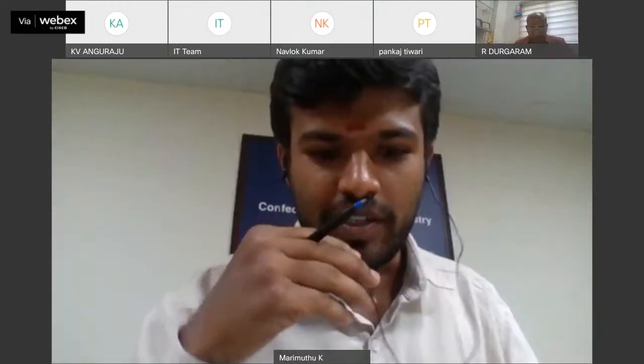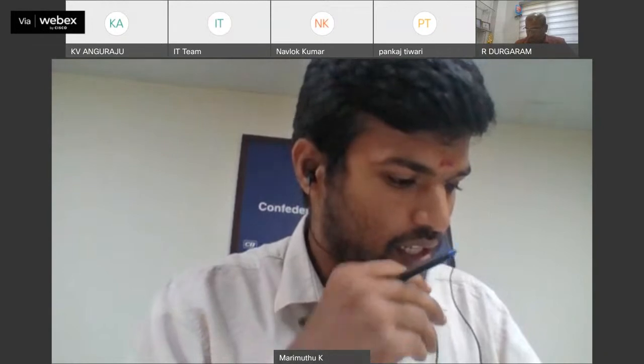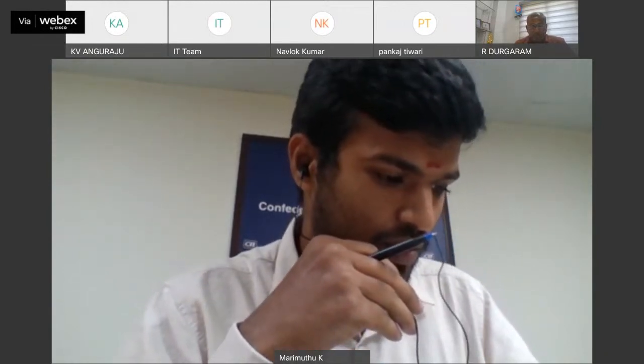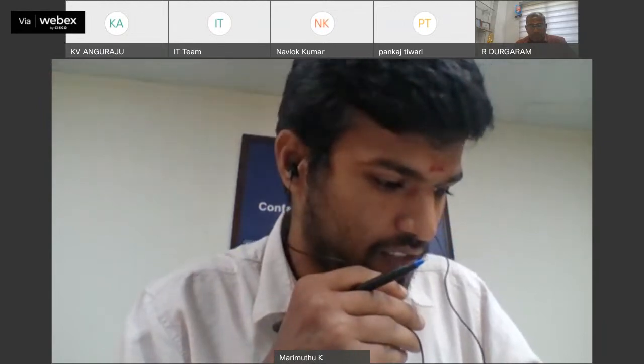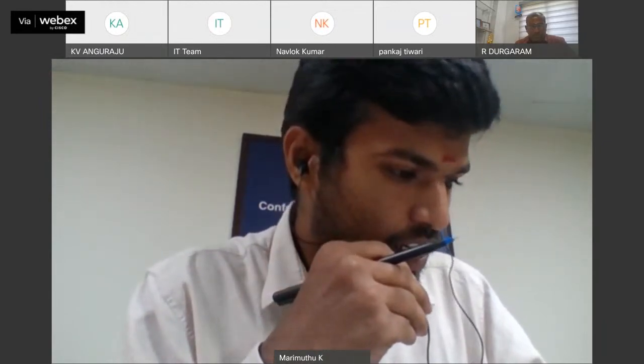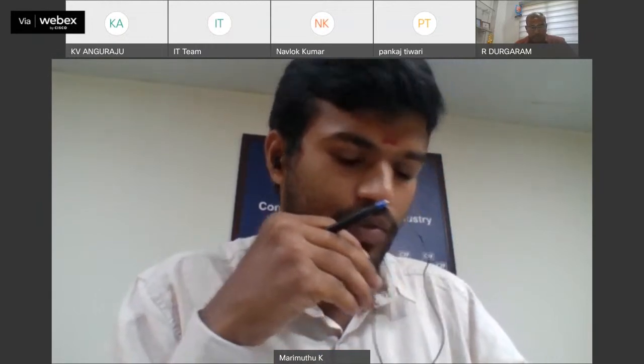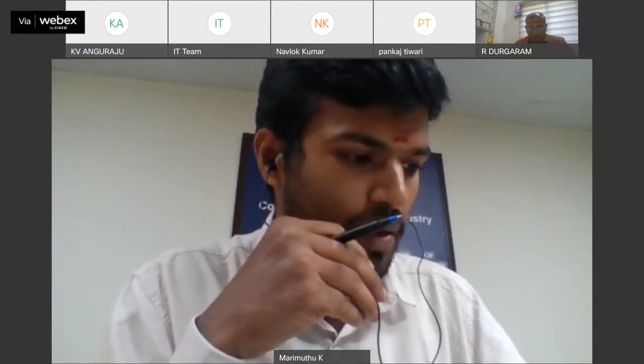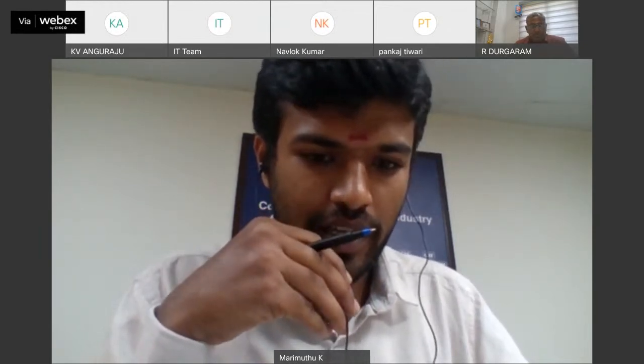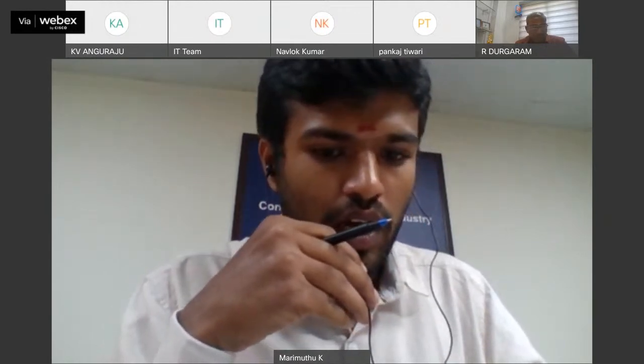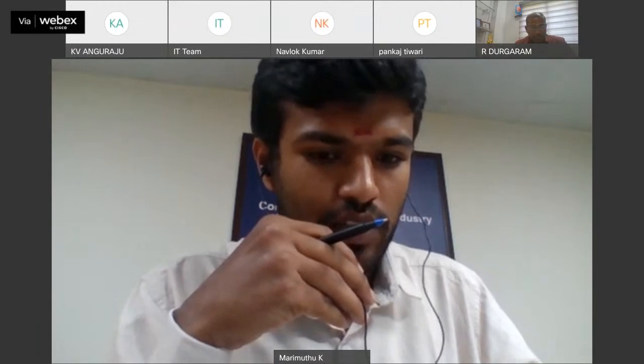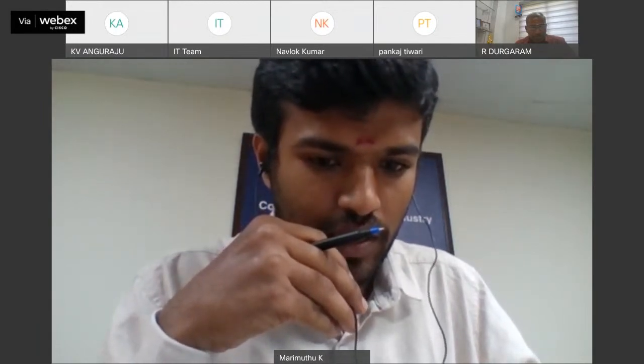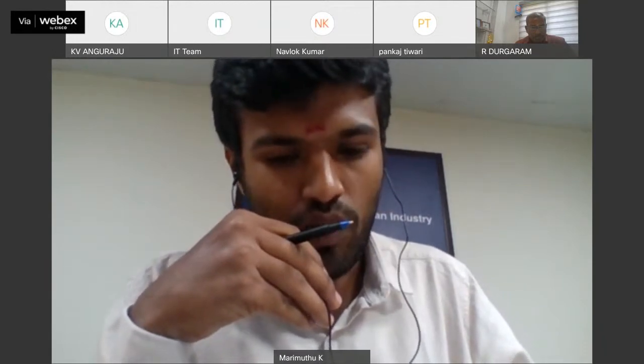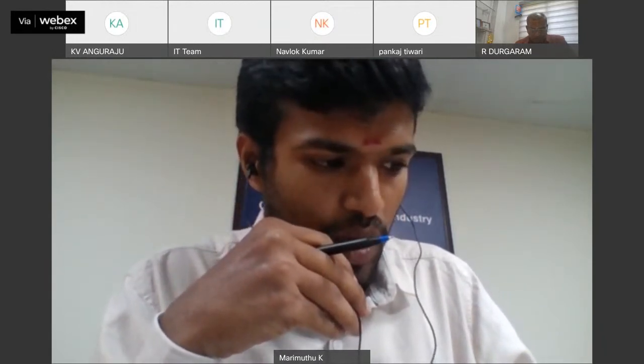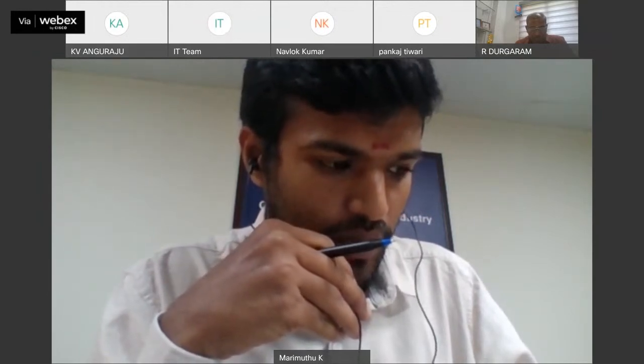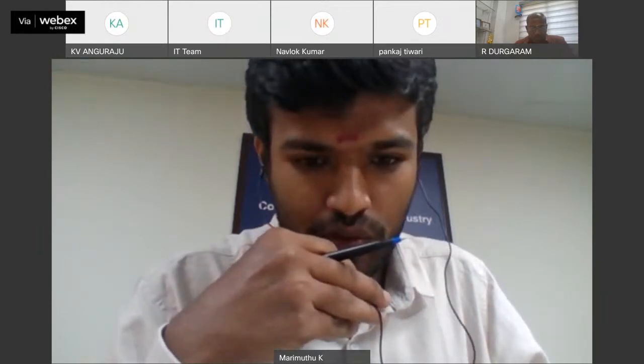Actually, it was a very interesting session. So I have received 3 questions from the participants. 2 questions to Mr. Ankuraj. The questions are related to the LP system bypassing. The PH boiler temperature input and output is decided based on the raw mill drying. If you want more temperature for raw mill drying, for example, the boiler is designed for 150, and I want the temperature 180 or 200, can I bypass the LP system? Will it impact my coils or not? So that is the one question.